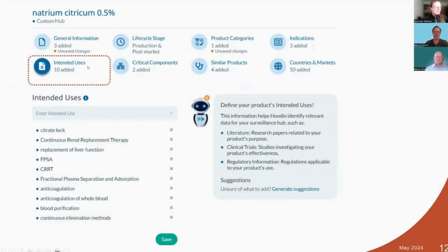Here, the thing that I find the most important is it needs to be set up by a person who knows the product, because what I need to begin with is the instructions for use and the certificates, and to find a correct classification, and the rule, and the purpose of use, indications, contraindications, and composition, and also the risk management file, because when I'm looking for some kind of very specific type of event, then I would absolutely need to understand where this kind of information is coming from.